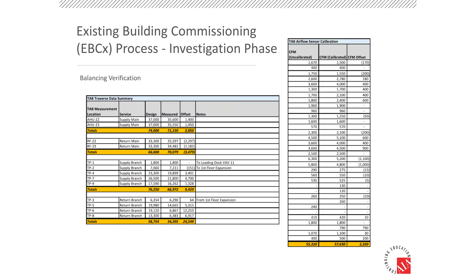All right, and the final part of our process for the investigation phase was a balancing verification. Again, very important, and this was where we really had the opportunity to look at the air distribution system as a whole. So we brought in a third-party person who came in, and we all sat down together and figured out, okay, where can we get the best data, the most useful data about the airflow in the distribution as a whole? And we came up with a number of different locations to take duct traverse readings at the mains, so the supply and return main coming off of the air handling units, but also at every major branch duct. And I think there aren't that many, but 8 branch ducts. So the balancer was there for 2 or 3 days, just taking duct traverse readings and gathering that information.